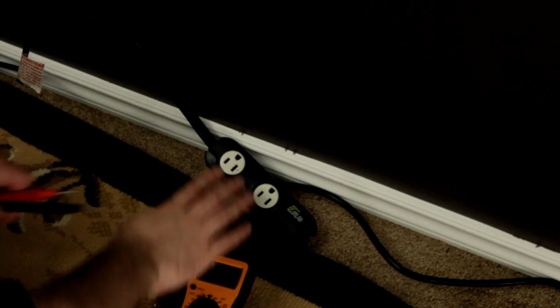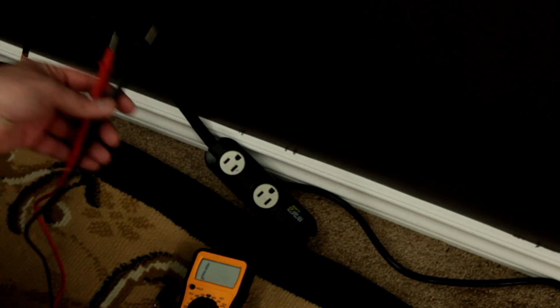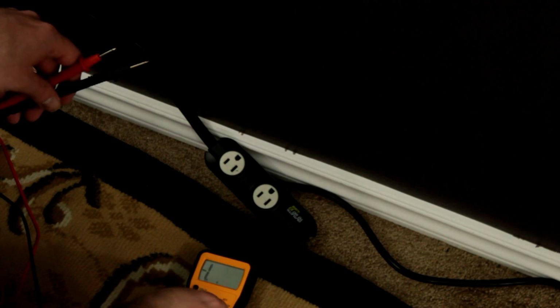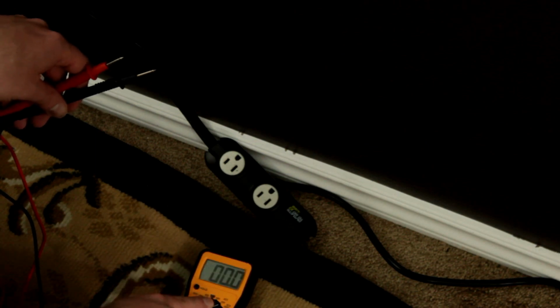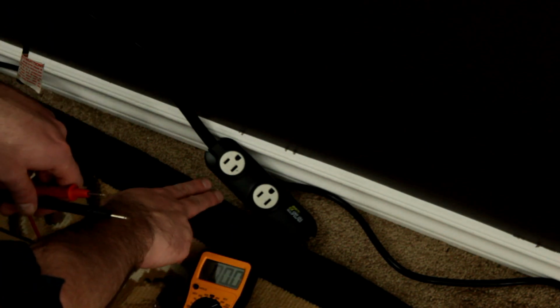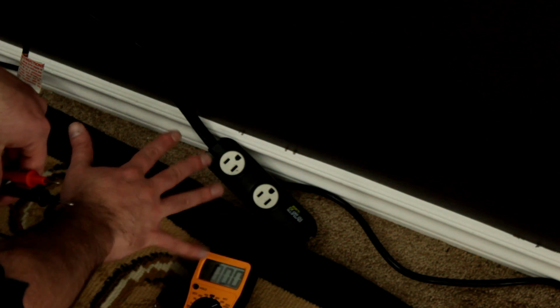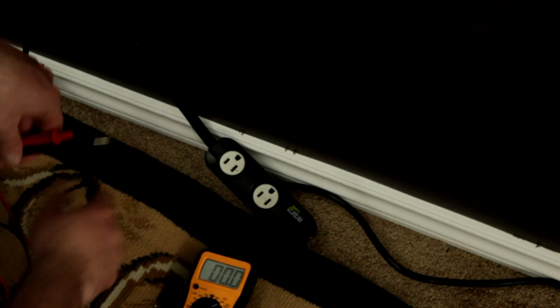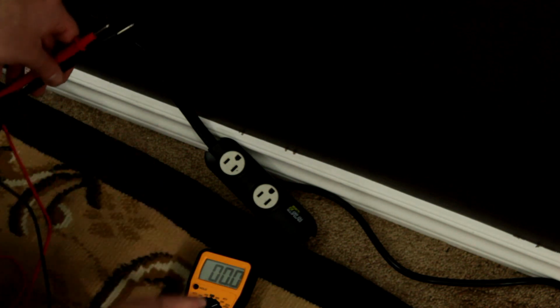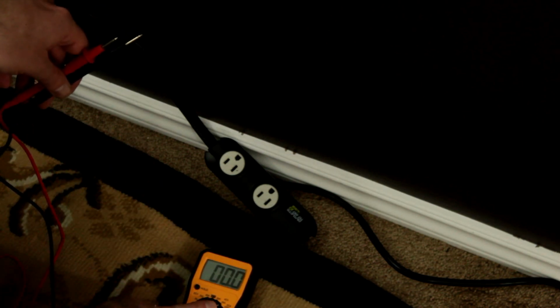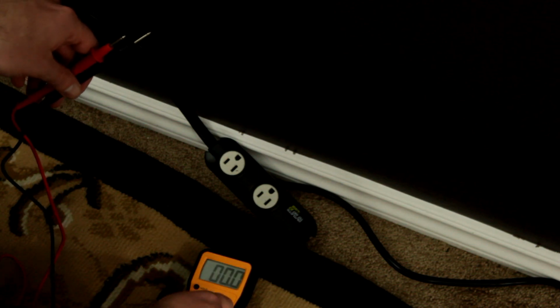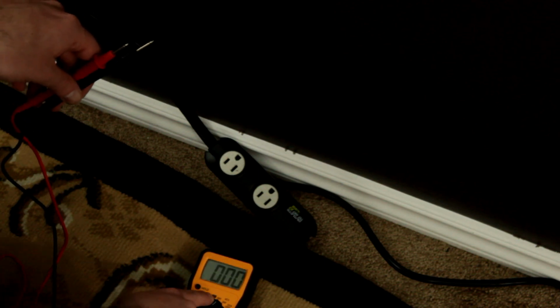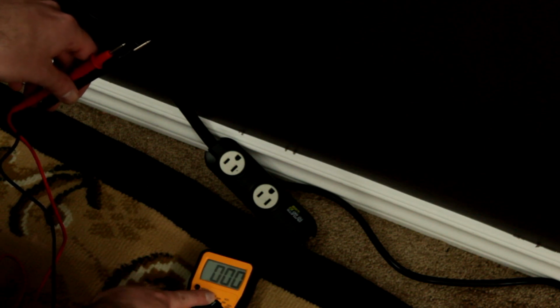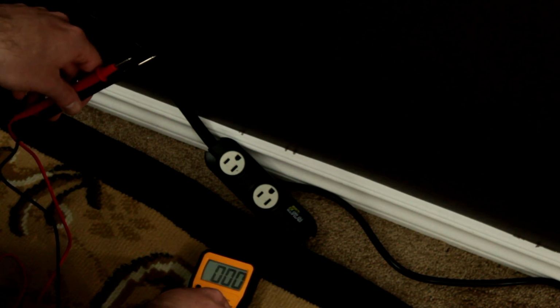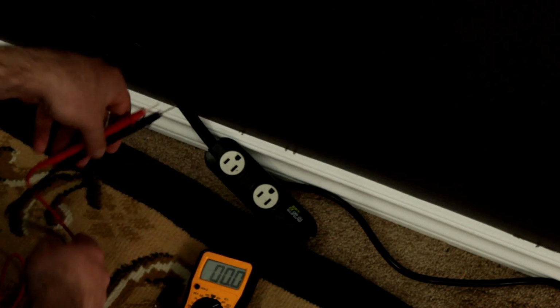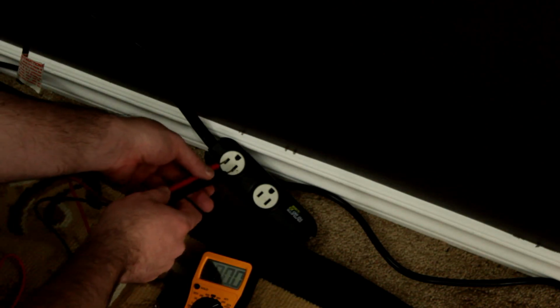Okay, so here we have a standard power strip, and we've got our multimeter, and we're going to set it to AC voltage in the 200 volt range. Now, this should be 120 volt-ish, anywhere between 110 and 120. And so we always want to set the multimeter to a higher voltage than what the rating is. If you're unsure, always start at the highest setting. In this particular case, that'd be 600 volts AC. But I know that there's no chance that this is the 240 line, so I'm setting it to 200.